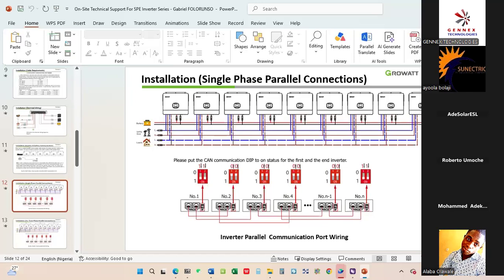So what does that mean? For the DIP switch of the first inverter, you must activate it by turning it on - you can see there 1 1, right? Then the last born is also turned on. But in between the line of inverters hooked up, everything can be 0. If not, that inverter will not work from now till tomorrow - you'll just be calling people. You failed to activate the DIP switch, so it's very, very important.